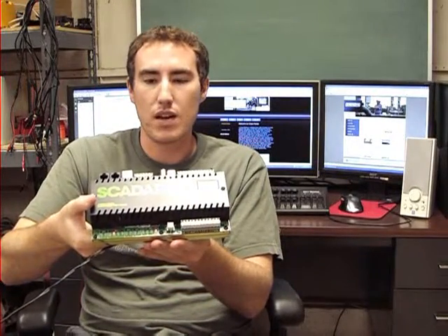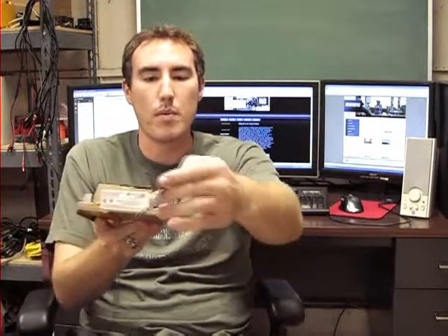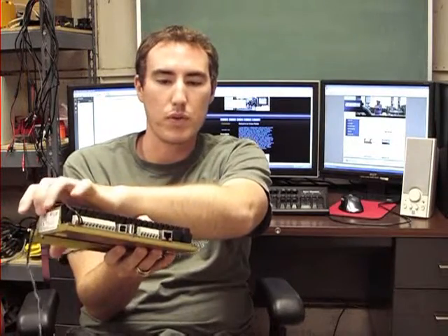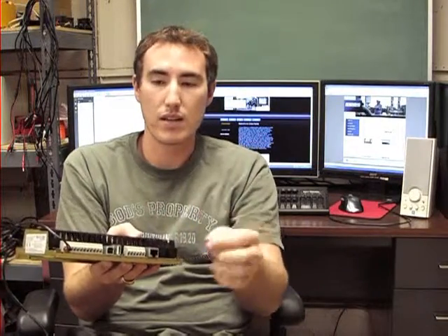So I would like to first start out and show you what we're actually going to be using so that we can also monitor a natural gas compressor. And I want to start out with the SCADAPack 350, which is a processor with a 32-bit architecture, and that's actually what we're going to be programming on. It has quite a few inputs and outputs that are digital and analog both, and then we also have RS-232s, RS-485, and then USB and Ethernet as well. So we'll be able to communicate through those ports.